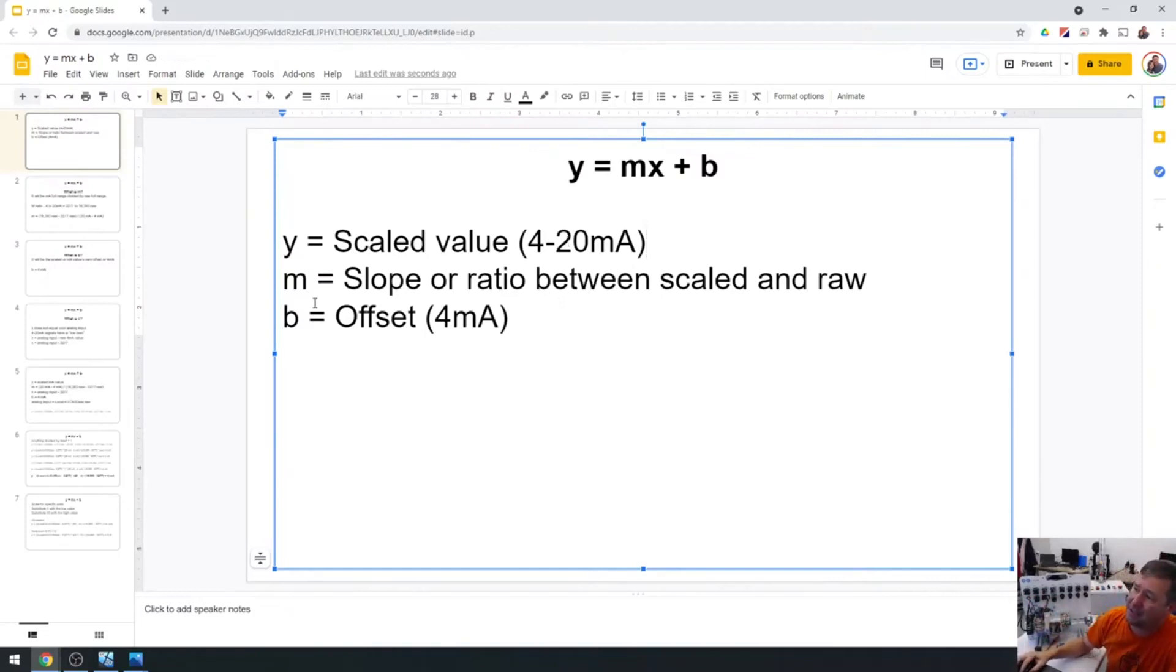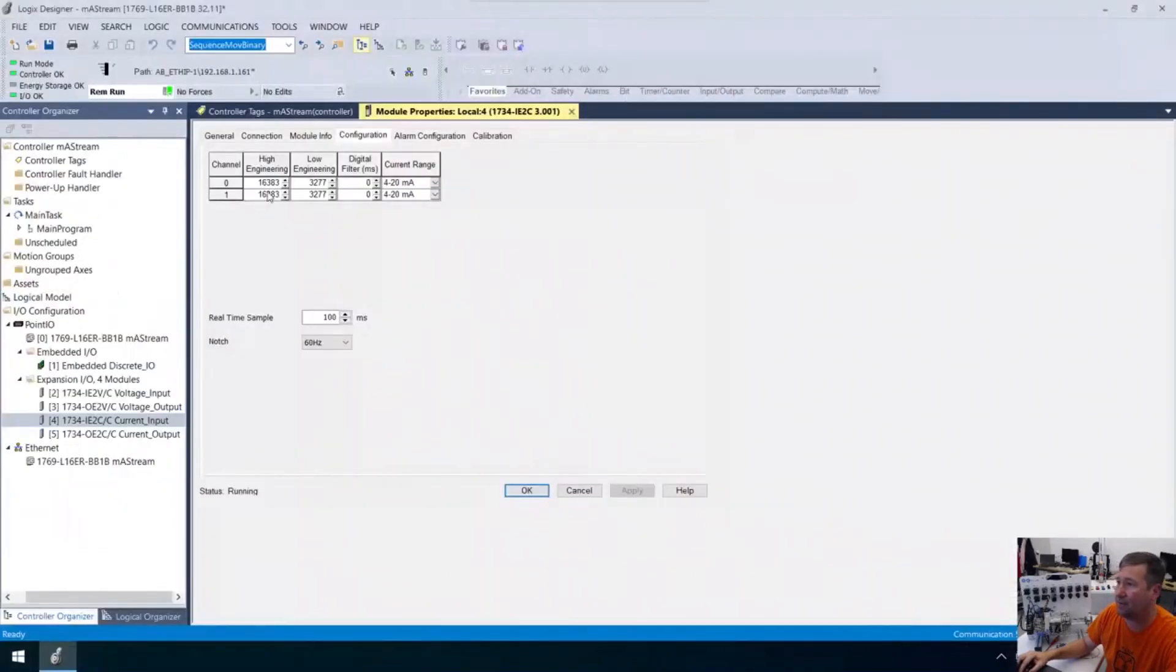And then we're going to have a slope here. And that's M. And this is going to be the ratio between our scaled value and our raw value. So we're going to figure out how many units of that 16,383 to 3277 are going to equal this 4 to 20 milliamp signal. So we're going to need to figure that slope out there.